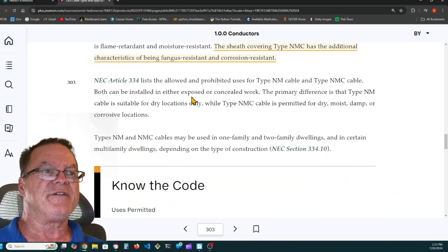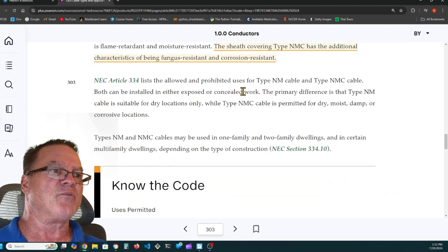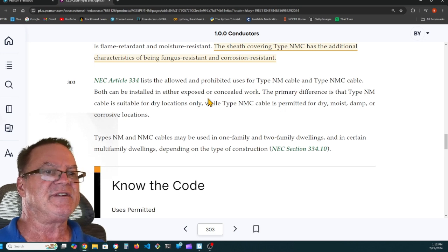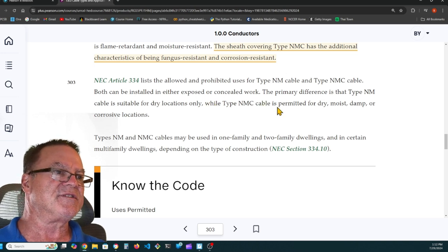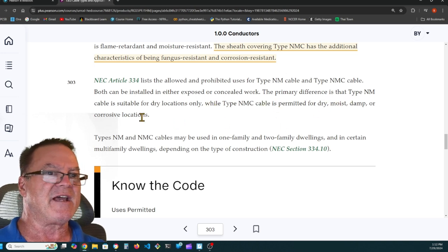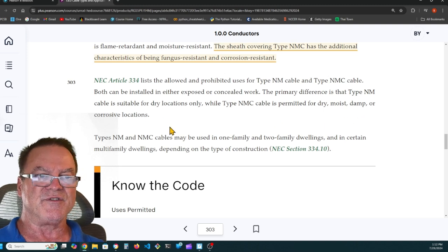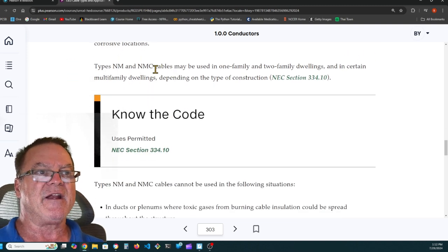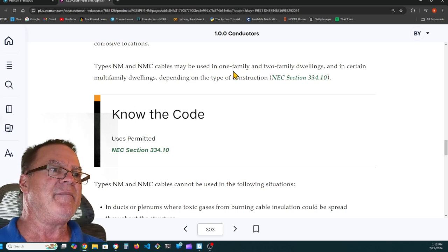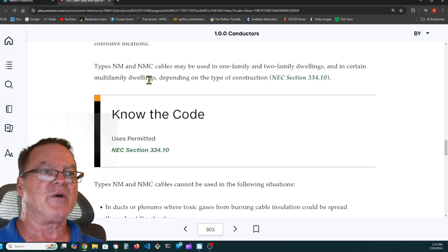NEC Article 334 lists the allowed and prohibited uses of type NM and NMC cable. Both can be installed in either exposed or concealed work. The primary difference is that type NM cable is suitable for dry locations only, while type NMC cable is permitted for dry, moist, damp, or corrosive locations.